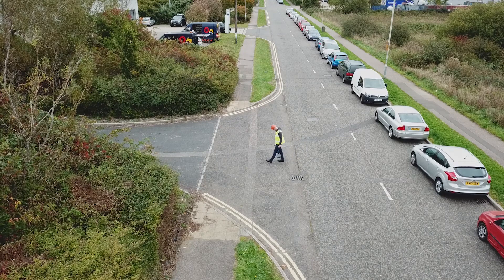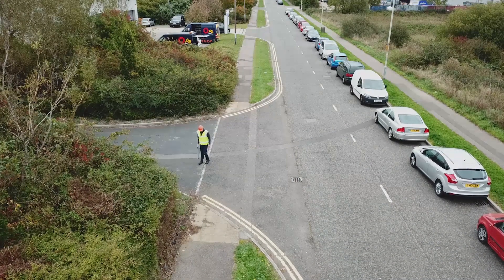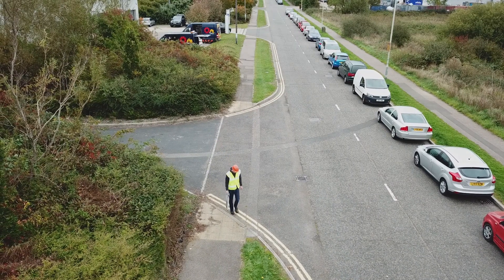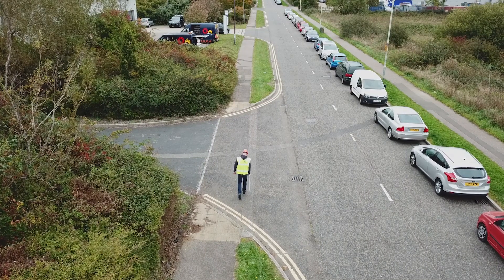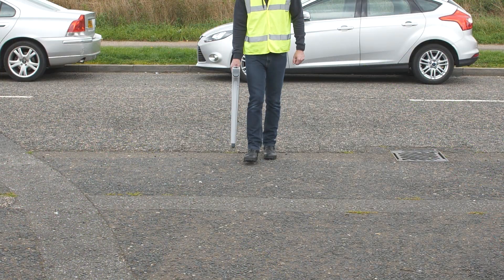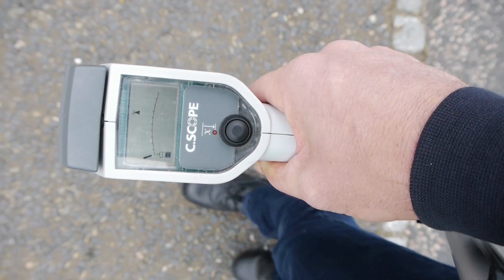Ideally, the locator blade needs to be orientated at right angles to the metal pipes and cables to be detected, but it can cross at a lesser angle and still detect their signal. It is only if the blade is exactly parallel to the buried service that it may not detect the radio signal. Take care not to swing the blade when scanning, but keep it close to your side, pointing directly down. The locator will give an audible and visible response when a radio signal is detected.